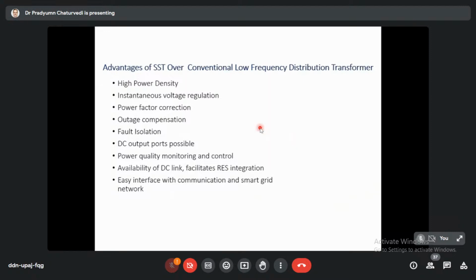So these are a few advantages of SST over traditional transformer: high power density, instantaneous voltage regulation, power factor correction, outage compensation, isolation, DC ports available, power quality monitoring and control, because we are able to monitor and control the variables through our digital controllers. Availability of DC links will facilitate RES integration and easy interface with communication and smart grid networks.